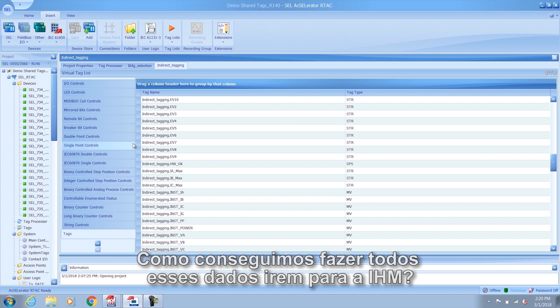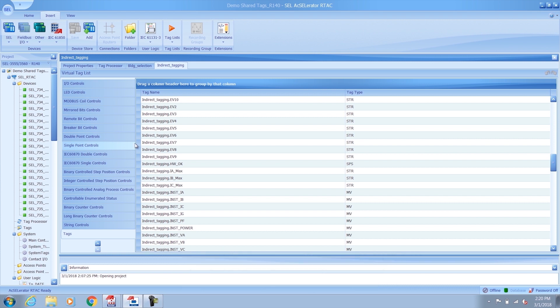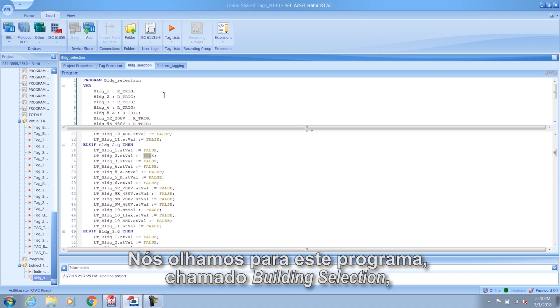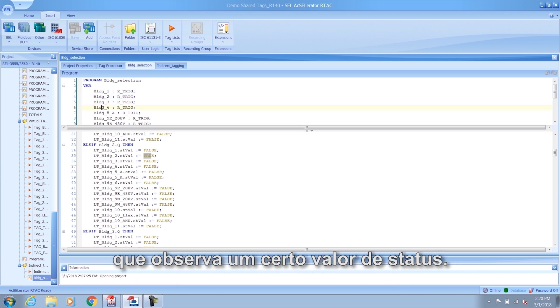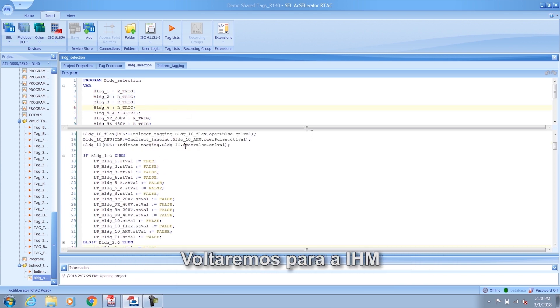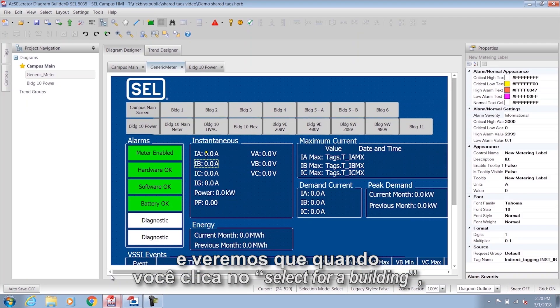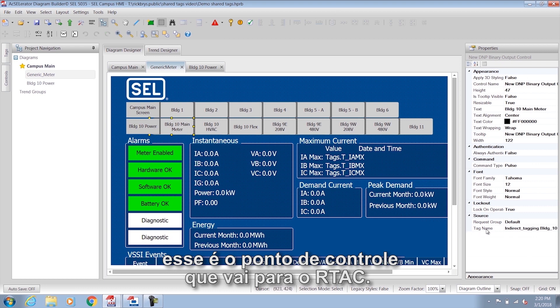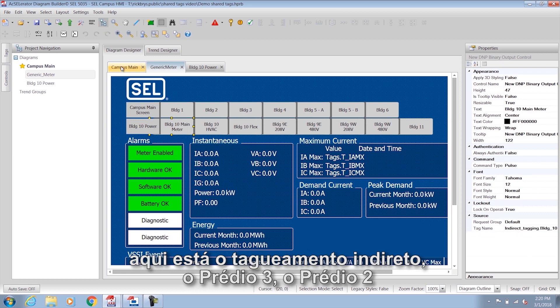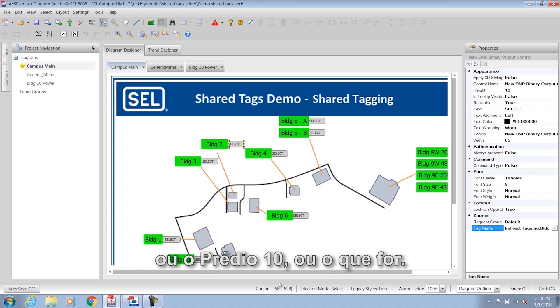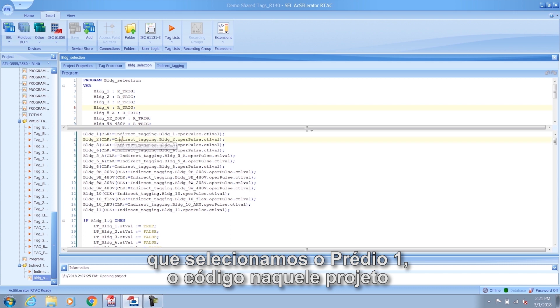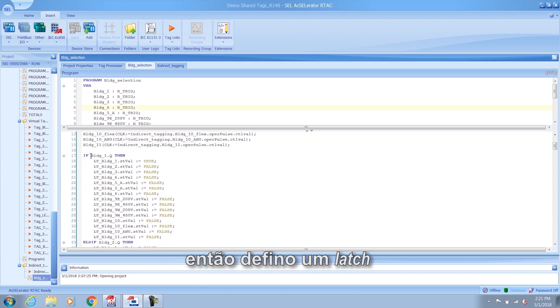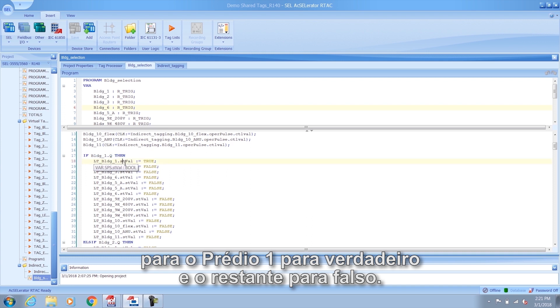Now, how do we get that data to the HMI? We look at a program called building selection. There's a rising edge trigger function block that looks at a certain status value. Back in the HMI, when you click 'select' for a building, that is a control point going to the RTAC — indirect tagging building 3, building 2, building 10, or whichever one it is. Back in that program, the rising edge trigger is detected and, for example, if we select building 1, the code sets a latch for building 1 to true and the rest to false.